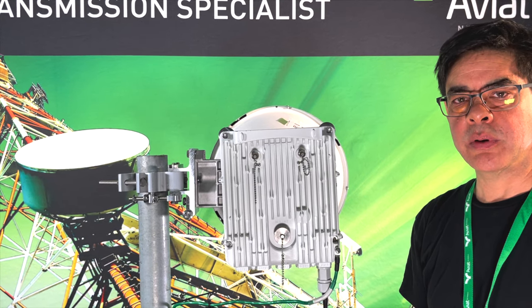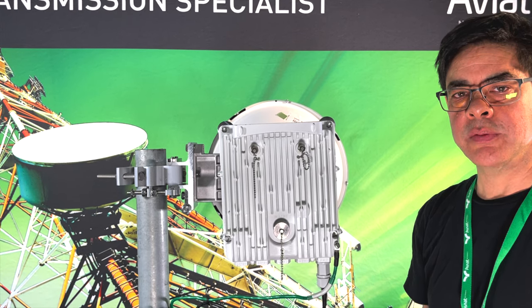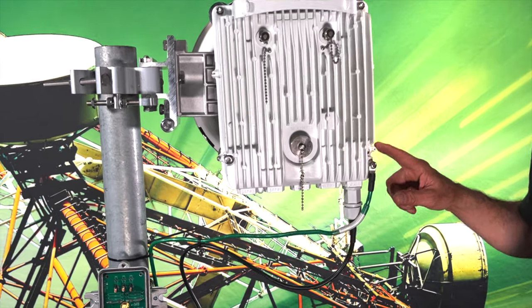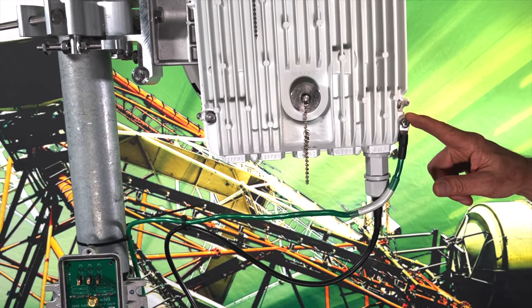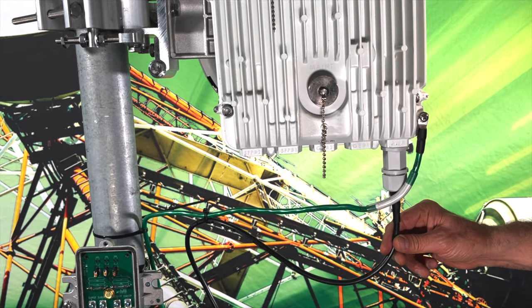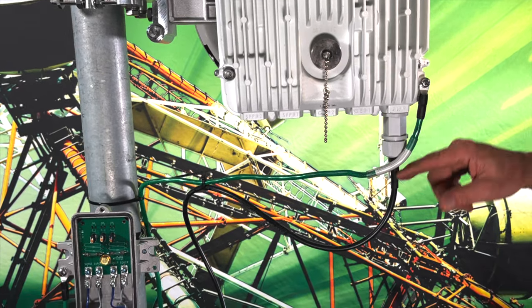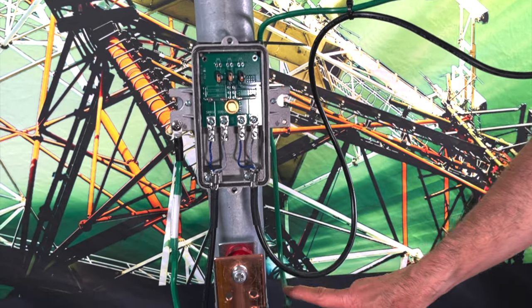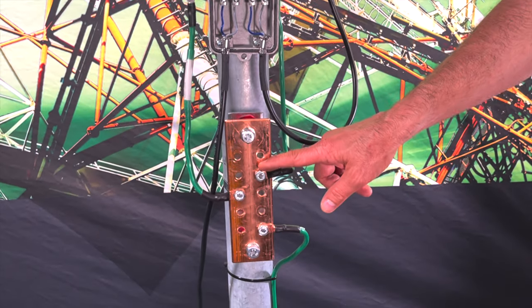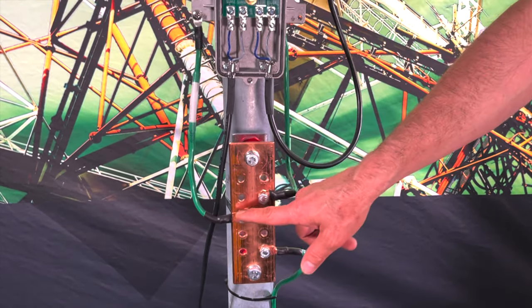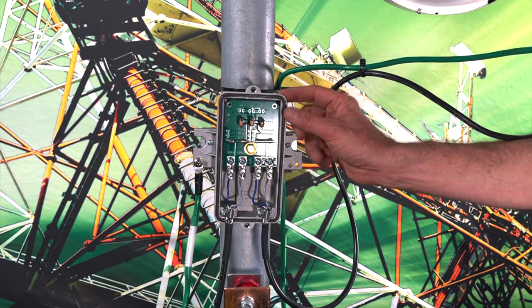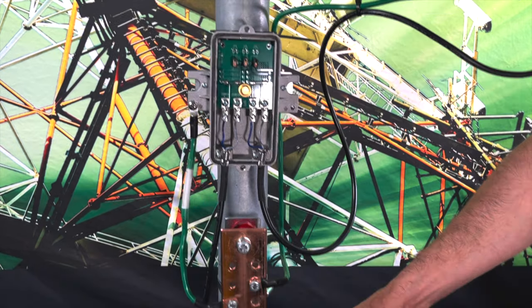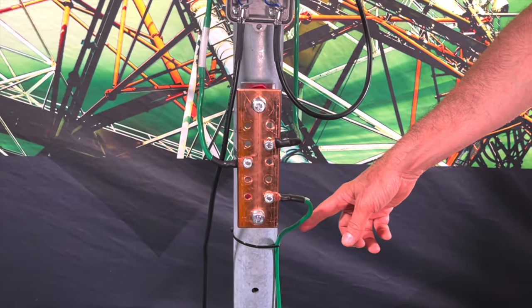Now that we've installed all the components, I'm going to walk you through and show you exactly what we've done. The first step, again, was to connect up our DC ground wire to the ground stud on the WTM radio. We also installed our DC power wire into the power part of the radio. We're going to follow these cables down. We'll notice here the DC ground wire connects into our system ground bus bar. We've also got a second ground wire coming back up to our surge arrestor, so the chassis of that has been grounded. There's also the ground wire that goes down to our earth ground down the side of the tower.